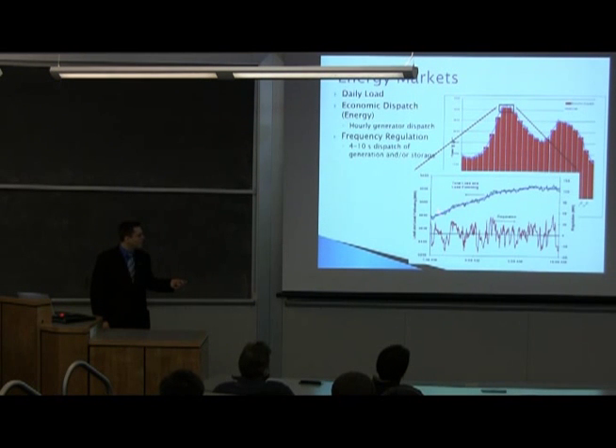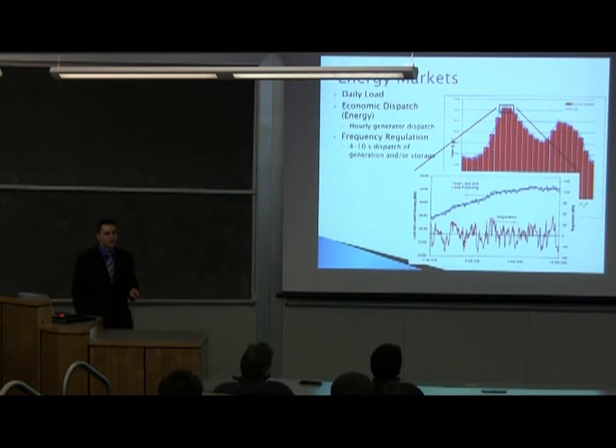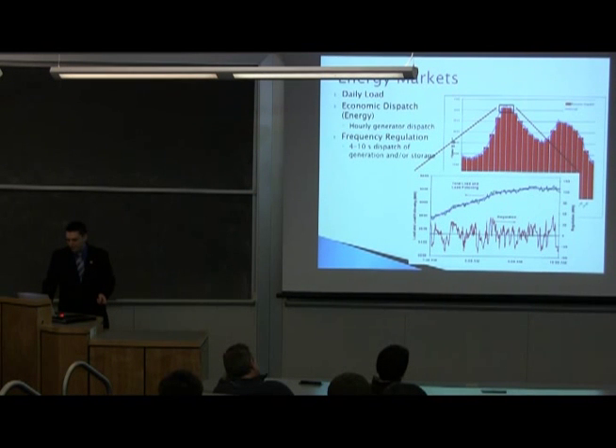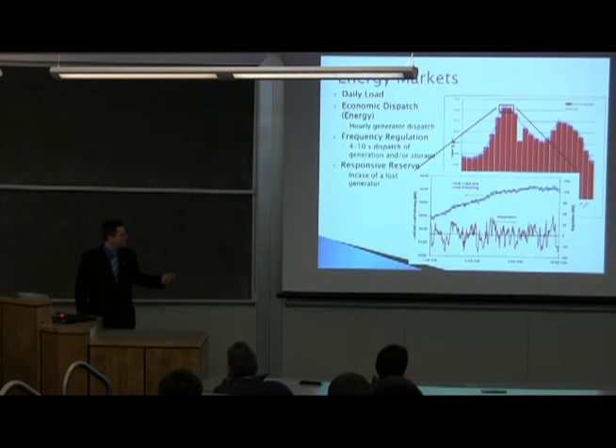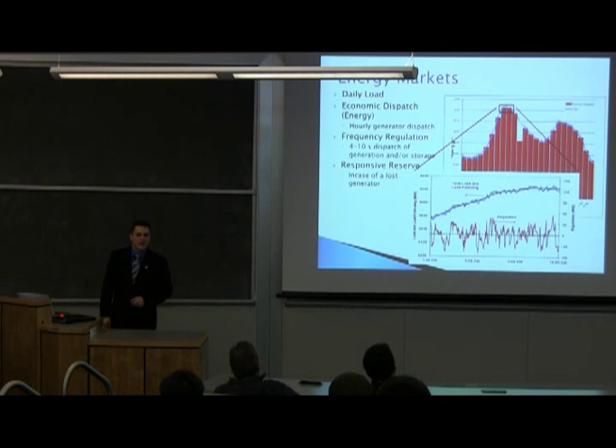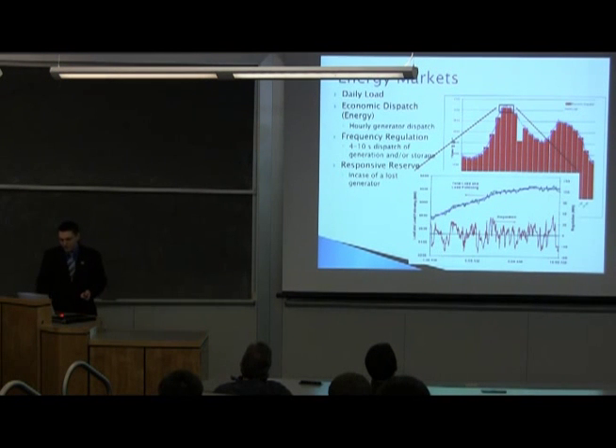If you zoom in on that top part, you see a high frequency component that's met by generators responding every 4 to 10 seconds to the fluctuations—called regulation. There's regulation up, meaning increased generation, and regulation down, meaning decreased generation. The gradual increase of load is taken care of through balancing markets, which have their own regulation market. And where suddenly a chunk of generation is lost, you have emergency reserves where other generators turn up to meet that loss of load—that's the responsive reserve market.